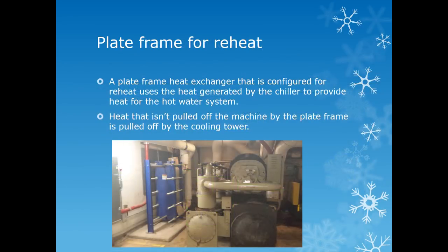The water system that has a plate frame heat exchanger configured for reheat uses the heat generated by the chiller to provide heat for the hot water system. Heat that isn't pulled off of the machine by the plate frame system is pulled off by the cooling tower. In the photo you can see a plate frame heat exchanger on the left hand side as well as a chiller on the right hand side. This is a very efficient way to provide hot water for a reheat system.